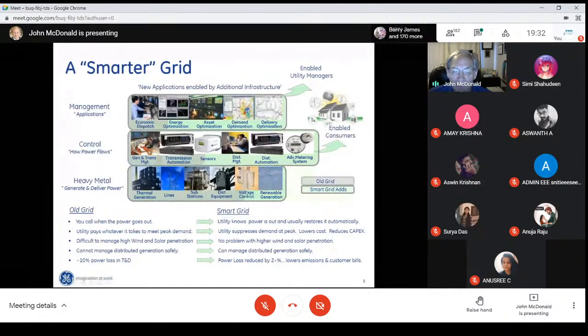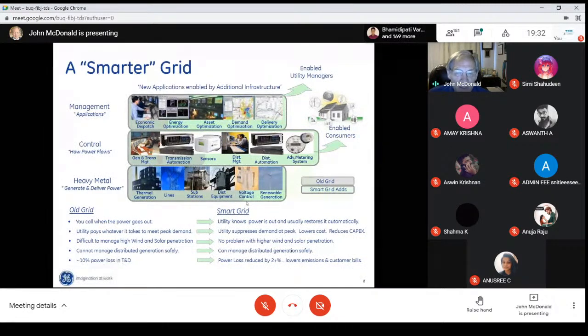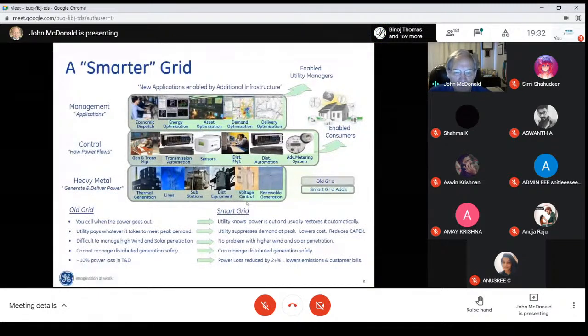You can see voltage control is shaded halfway. Well, I was doing voltage control in the 1970s, and it was for utilities. Let's say they were summer peaking, and on a hot summer day they were approaching their previous peak, and they didn't want to exceed that because they would have a financial penalty. So we could lower the secondary voltage, and load is directly proportional to voltage. This was called load management, and we would do this through voltage control.